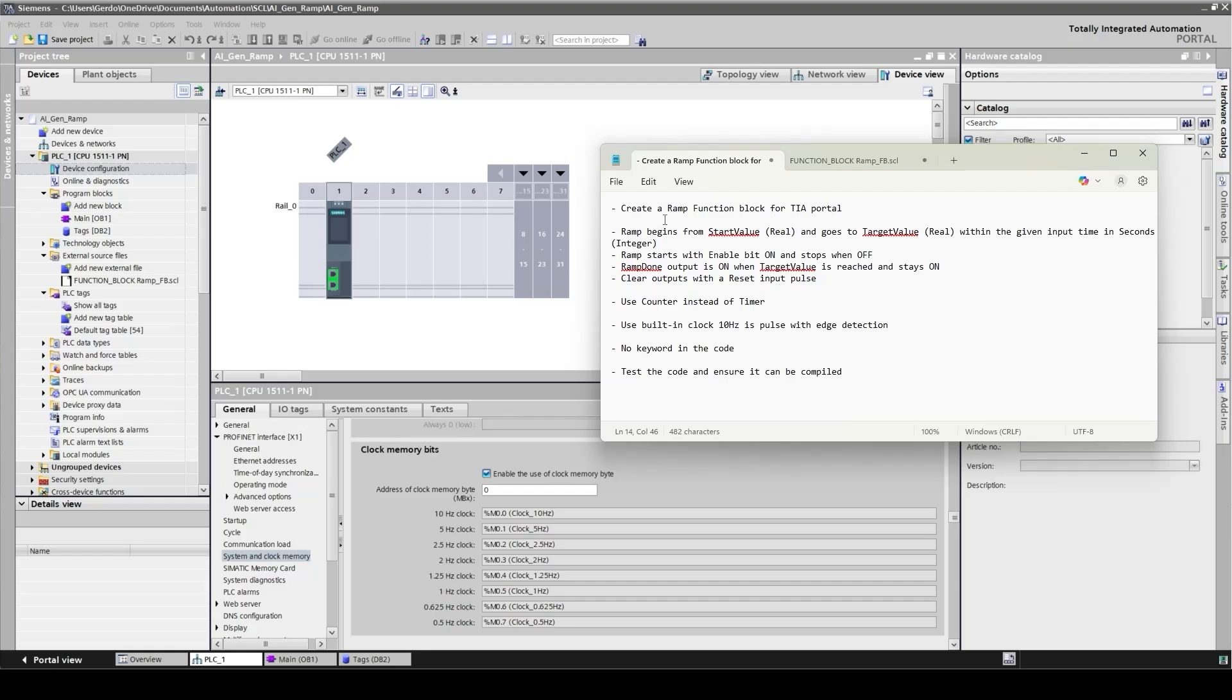I want a ramp function block for TIA Portal. My ramp function begins from a start value and goes to the target value with the given input time in seconds. I define start and target as real and my time input as integer. I want my ramp starts with the enable bit on and stops when it's off. I also want an output that turns on when the ramp reaches the target value, and I would like to be able to reset the output with an input pulse.